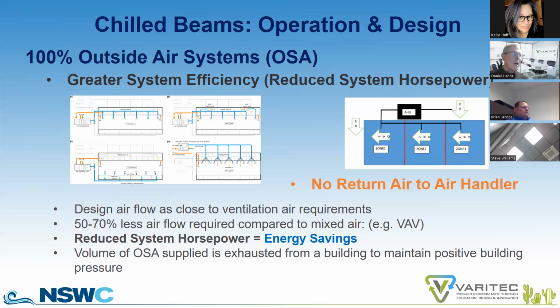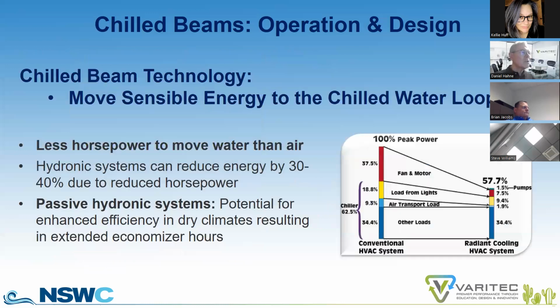The airflow designs can easily result in 50 to 70% less airflow than a conventional mixed air system, and there's significant energy savings to be had by the reduced amount of air serving that building. Nationally, we're seeing chill beam systems in energy modeling reports, and talking to Smith Group, HDR, and other designers, they're seeing roughly between 30 to 40% energy savings over medium pressure VAV systems.